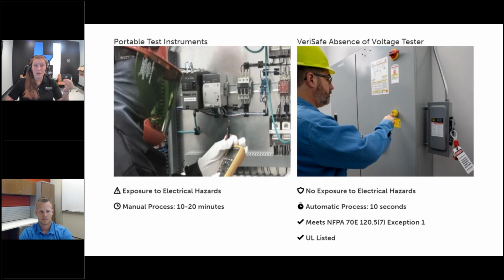You have to be exposed to those potential hazards, because there's no guarantee it's off until you verify it's off. So you have to suit up, you have to go through that process by hand. There are absence of voltage testers, such as VeriSafe, which is what we're going to be talking about today, that kind of take out a lot of those additional steps and removes the exposure piece. You don't have to open it up until you know it's off, which is actually really cool.